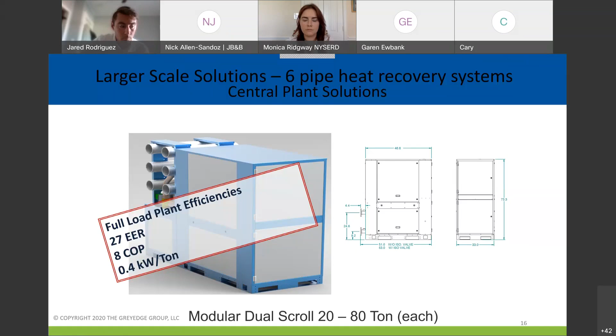And then when one loop or the other is imbalanced, when the loads in the two are imbalanced, it has two more pipes that let you go to a central loop, or to some sort of storage system, or even conventional equipment, so you can add or subtract energy. A conventional system would be a boiler and cooling tower, a ground source system might be the ground, might be thermal energy storage, and so forth. So we're constantly moving and recovering the wasted energy. And the reason for these efficiencies on the box has to do with how the system is handled.